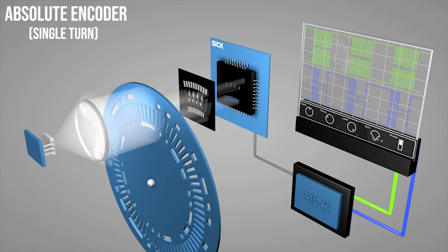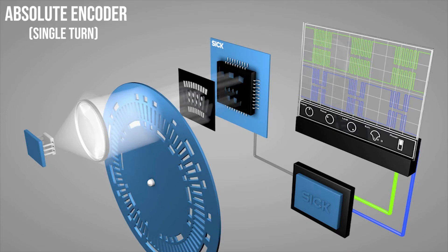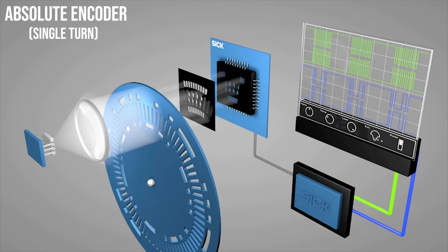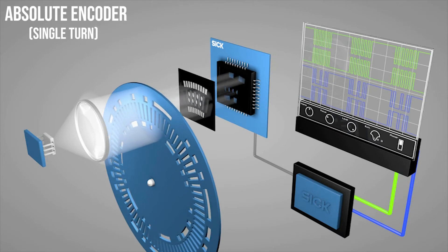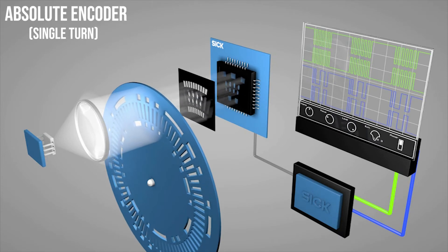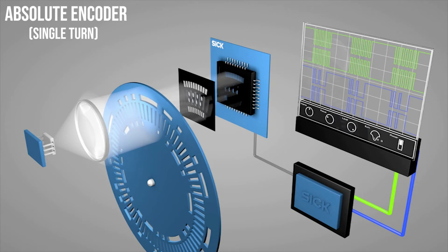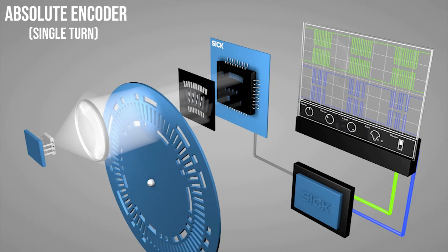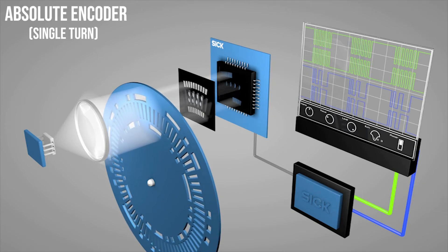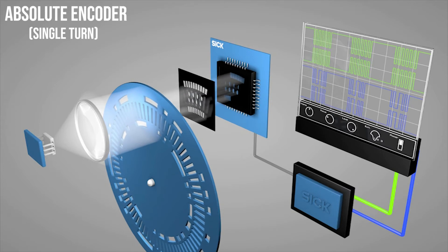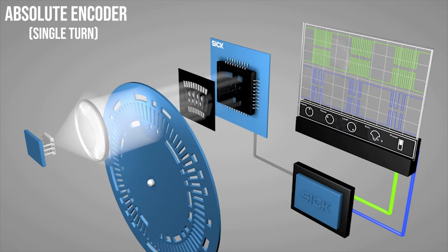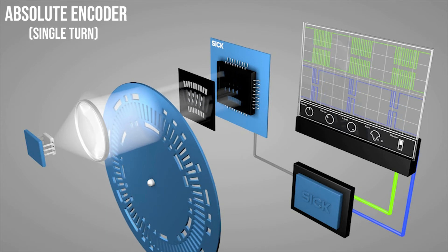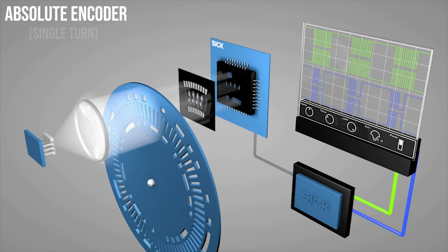The output of the encoder is no longer up to six channels with square wave pulses to indicate change of position and direction. The output of the absolute encoder is a unique address or position the encoder sees. Counting direction is very easy with the absolute encoder because all you have to do is watch as the address is building upward or falling downward.